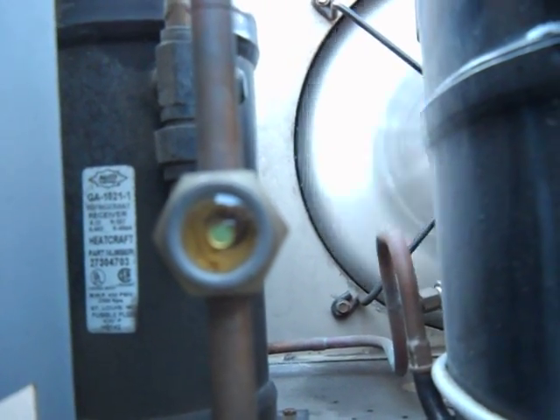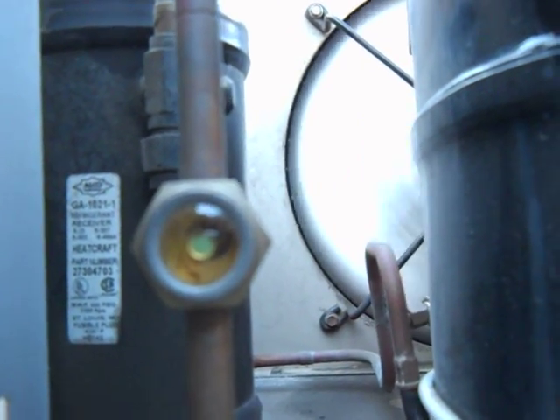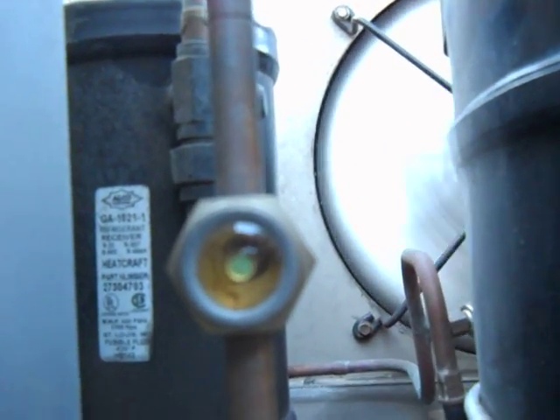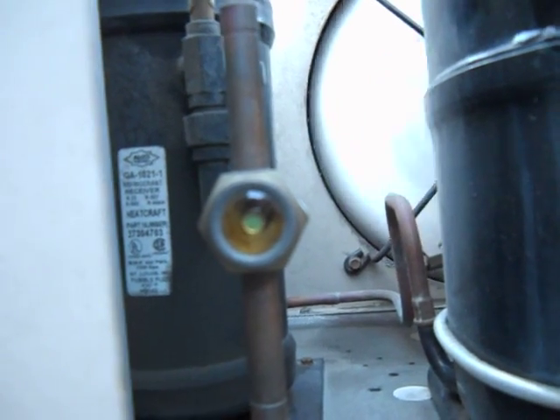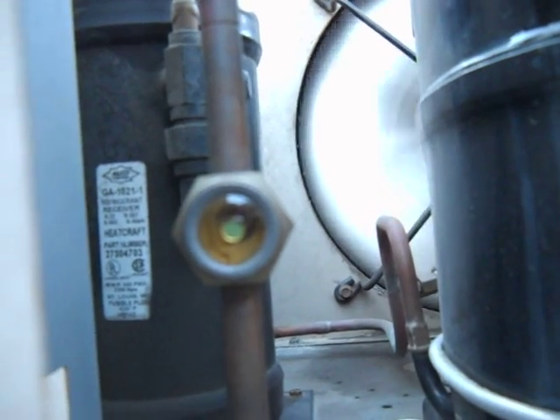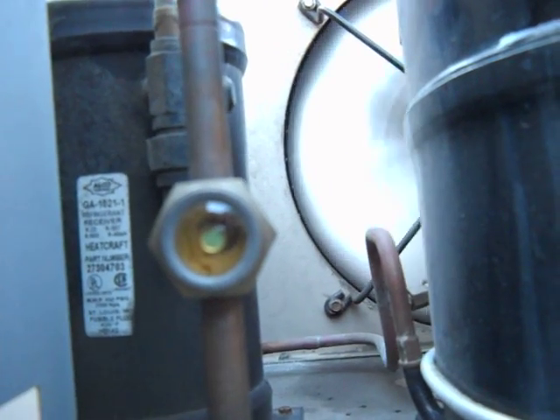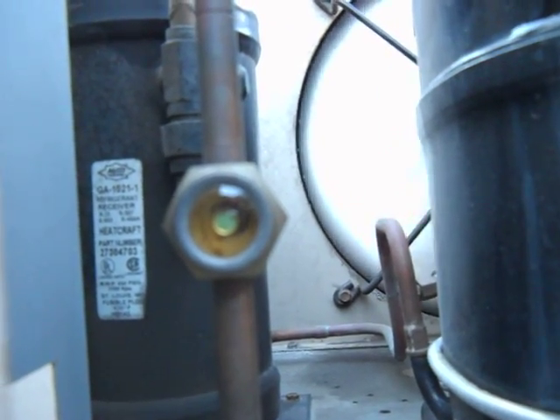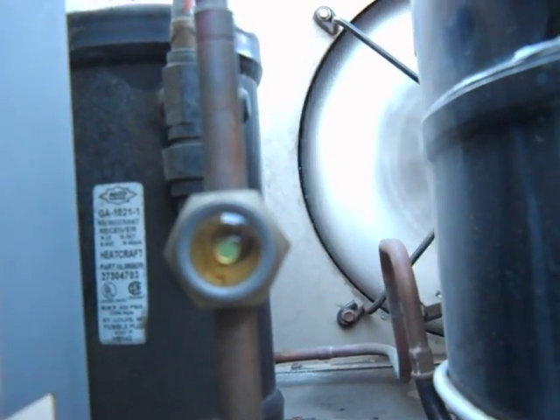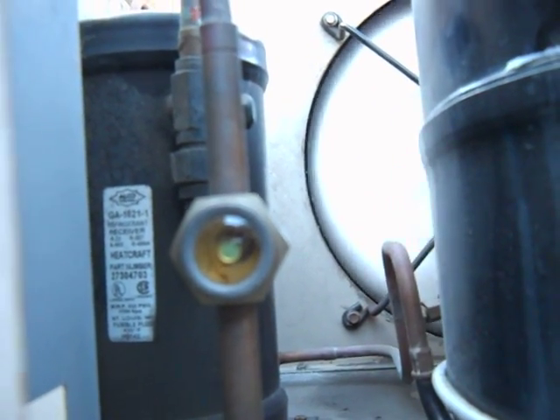That's when it's full. That's all charged up with refrigerant — that's a full sight glass — and that's what you want to see. You wait about five minutes to make sure everything's okay, be sure it stays that way. That's what a sight glass is supposed to look like when it's full of refrigerant.